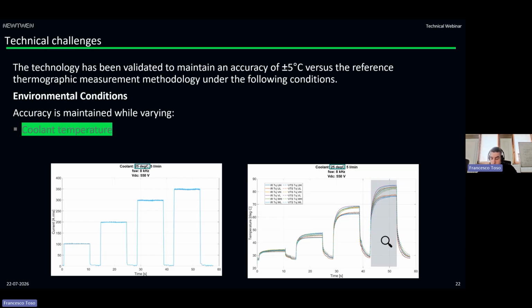Unfortunately, this temperature variation has not a linear behavior, in the sense that if we change now from 25 Celsius degree to 70 Celsius degree, the difference in the final junction temperature is not 45. It is more, because the system is non-linear. So if we change the coolant temperature, the junction temperature changes, and the power losses change. Your model has to take into account also about this. But most importantly, your model has to understand that you have a coolant temperature variation, even if it is not measured. That was the challenge. And as you can see, our model is capable of taking it.